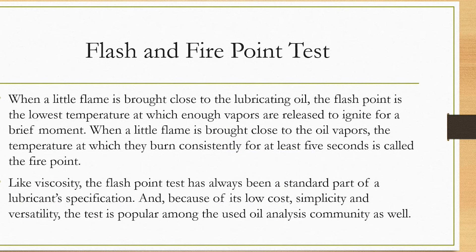Flash and fire point test: when a small flame is brought close to the lubricating oil, the flash point is the lowest temperature at which enough vapors are released to ignite for a brief moment. When a small flame is brought close to the oil vapors, the temperature at which they burn consistently for at least 5 seconds is called the fire point.